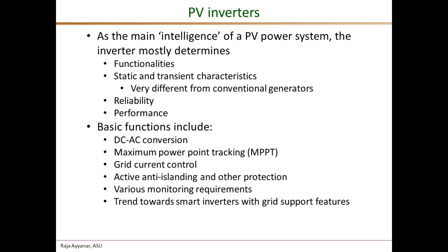The inverter needs to perform several protection functions, chief among them being active anti-islanding, which is a safety issue. They also perform various monitoring functions to relay power and energy production data. The recent trend has been to design smart inverters that can provide grid support features both at the transmission level and increasingly at the distribution level, in order to increase the hosting capacity of distribution feeders.